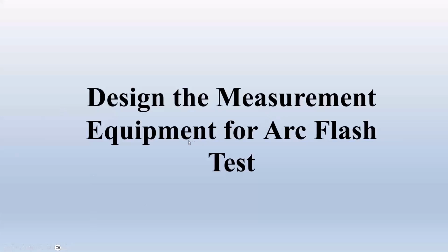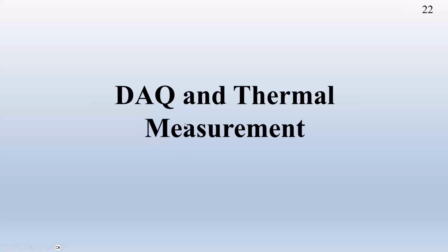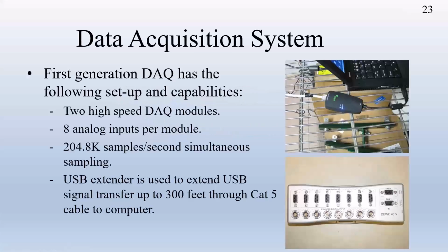Okay, so this is the measurement equipment for the arc flash test. The first one, of course, is that you have to collect the data, so the data acquisition system and the thermal measurement system. At the beginning we used an off-the-shelf product with a USB connection. According to the spec, it was pretty good. The sampling rate is more than 200K, and they give you 8 analog channels.